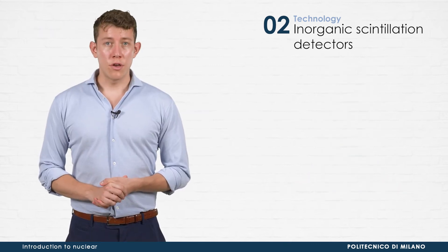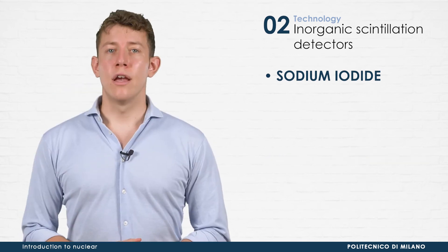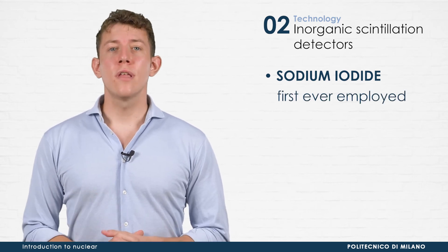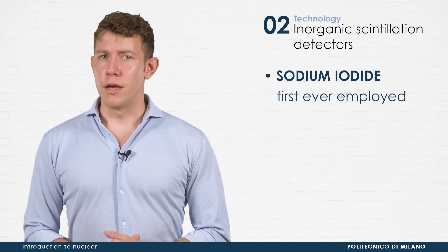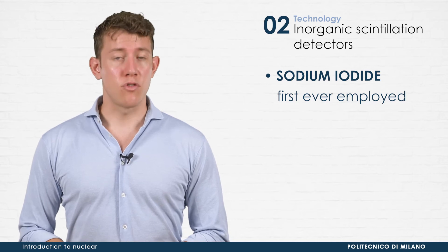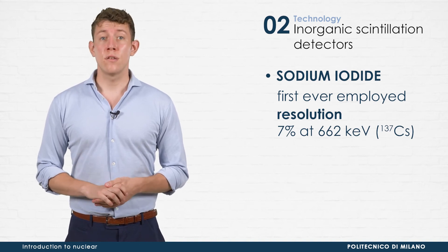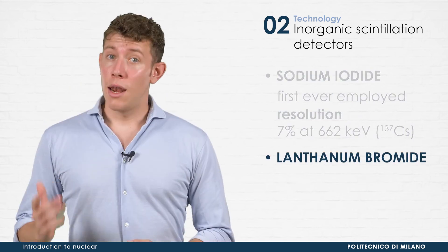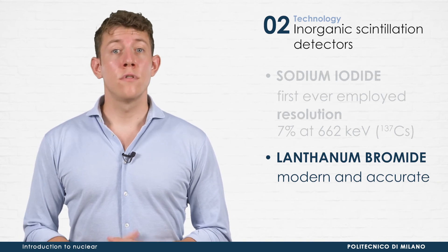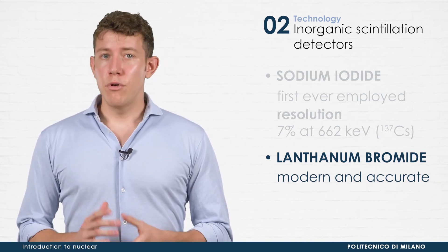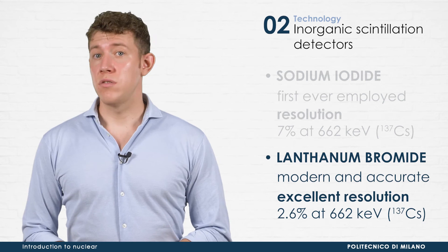The two most important scintillation detectors are sodium iodide and lanthanum bromide. Sodium iodide with thallium activation was the first ever employed scintillating material for gamma spectroscopy in 1948, and still finds use in modern gamma spectroscopy. It is characterized by an energy resolution of about 7 percent at 662 kilo electron volts. Lanthanum bromide with cerium activation is a more modern and more accurate alternative, providing an excellent resolution of around 2.6 percent at 662 kilo electron volts.